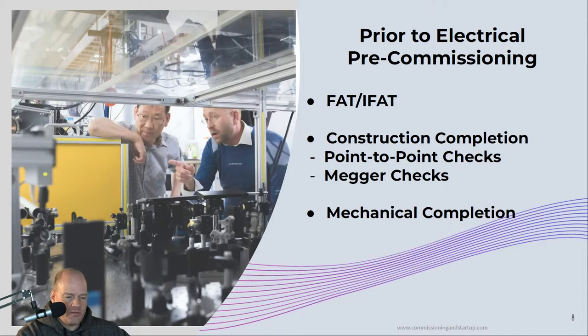Particularly when systems have software involved, we need to be doing an integration of the hardware and the software in the factory before equipment is shipped to site. It's too late to only be integrating software on-site after equipment has been installed — all that risk is transferred to later in the project, making on-site commissioning much more difficult. Testing in the factory isn't a replacement for testing on-site; we need to do both. But anything we can test in advance mitigates risk so we don't have issues during on-site pre-commissioning and commissioning.